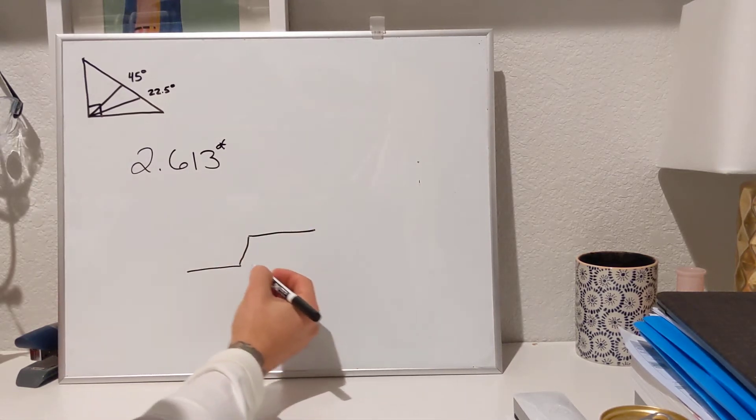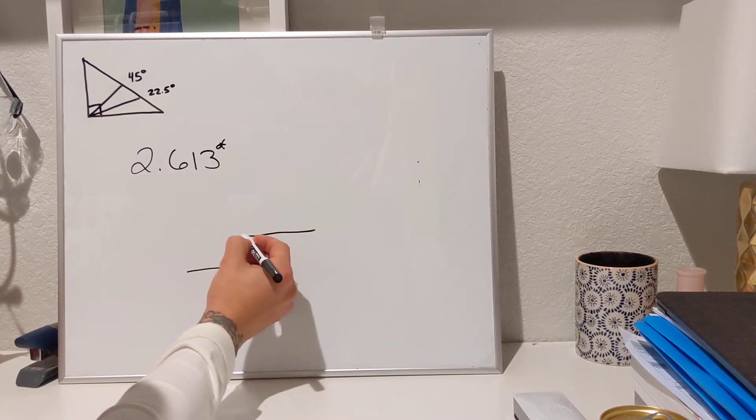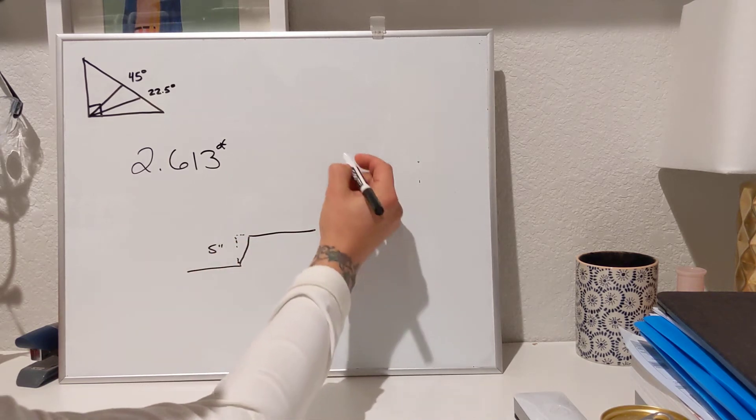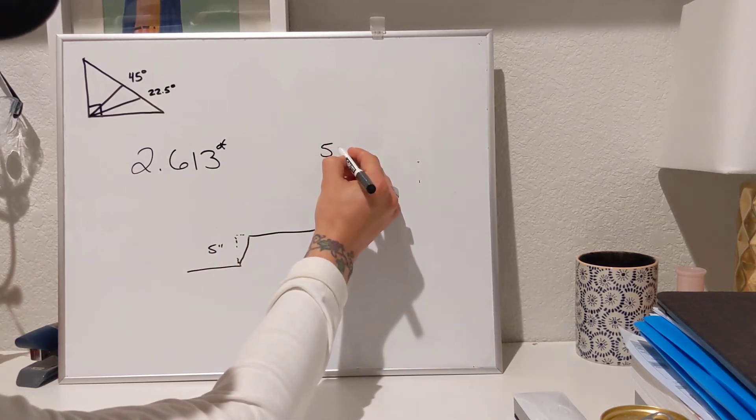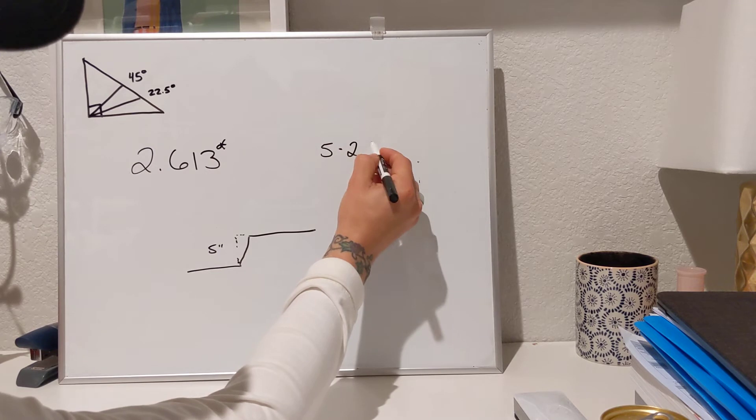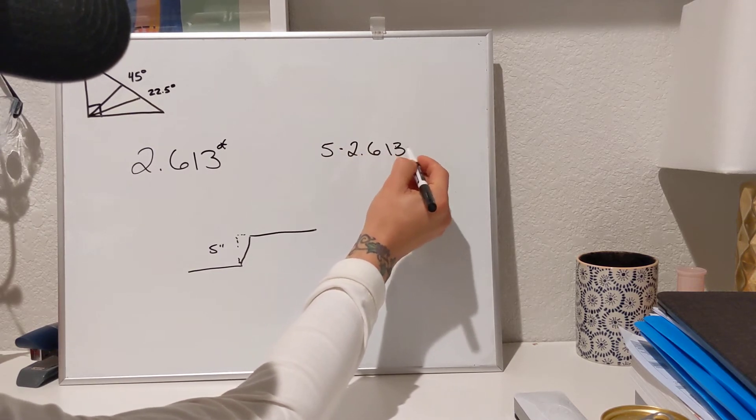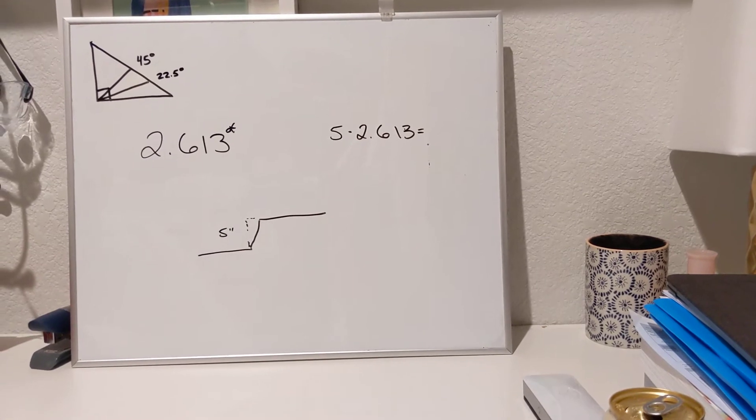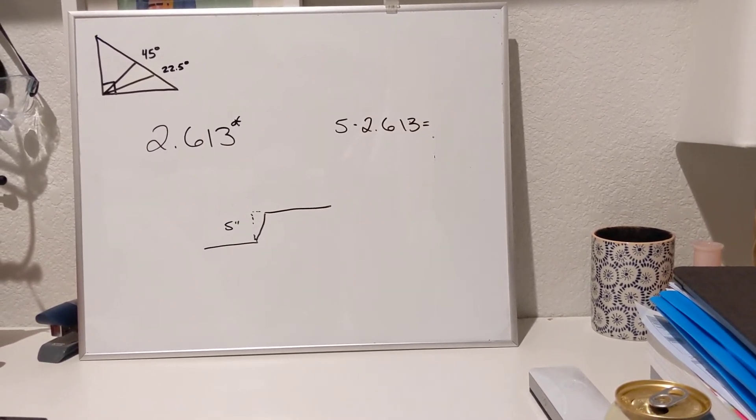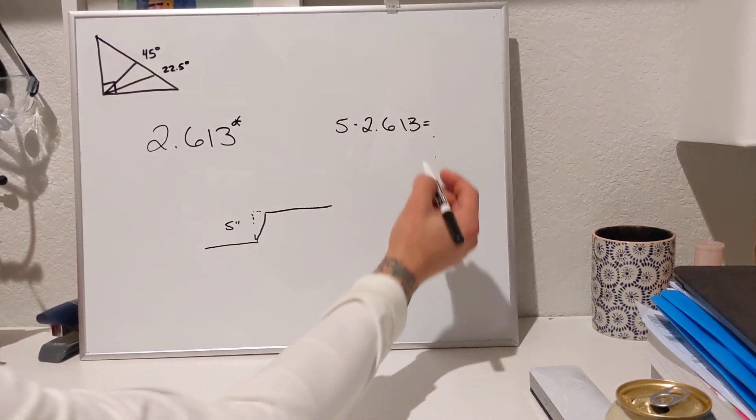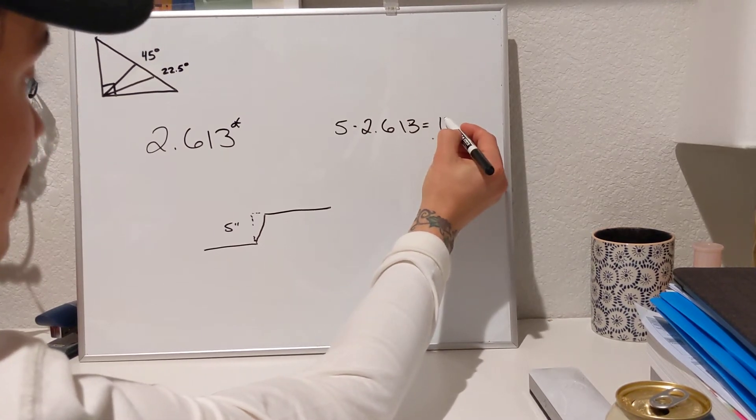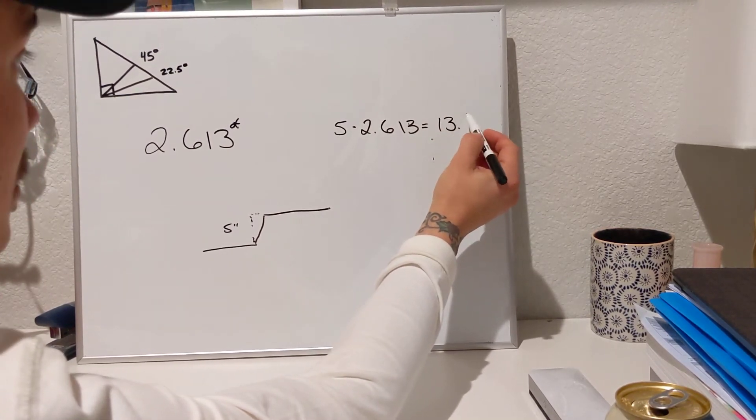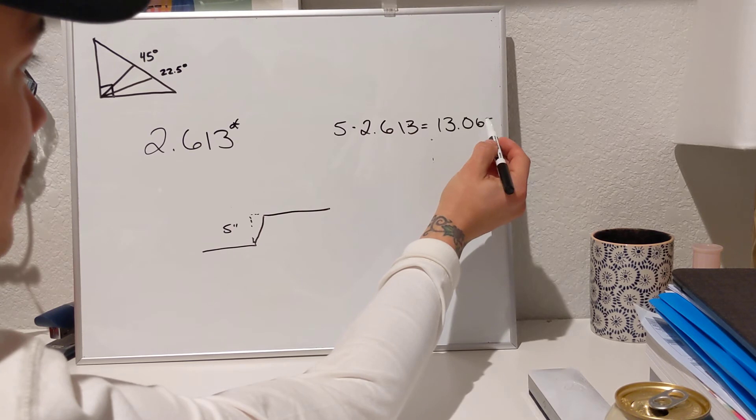So you're going to take, let's say, this distance between these two. It's going to be 5 inches. So you take 5 times 2.613 and that's going to give us our offset cut piece. So it's going to be 13.065.